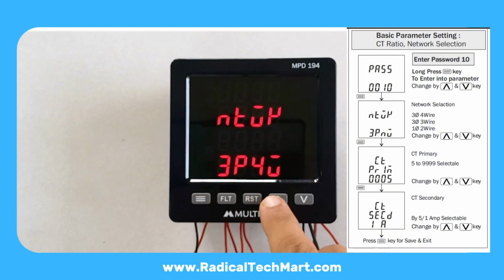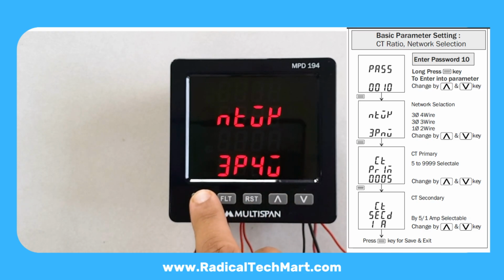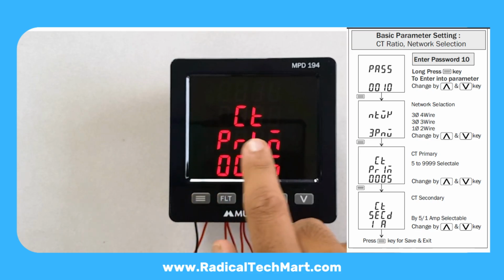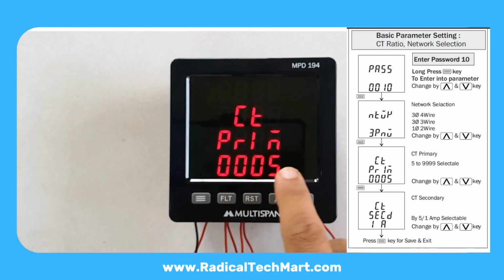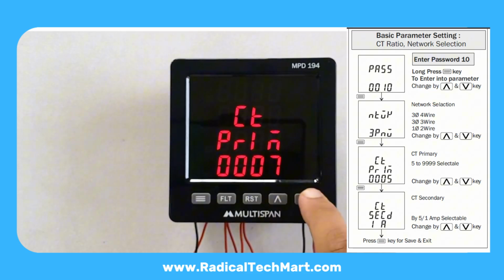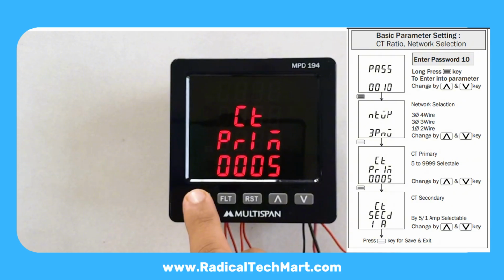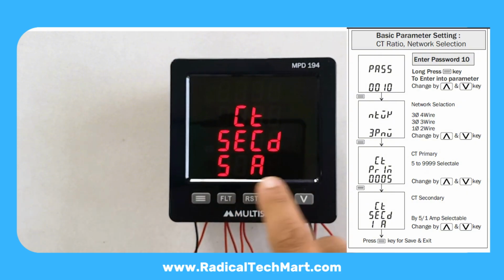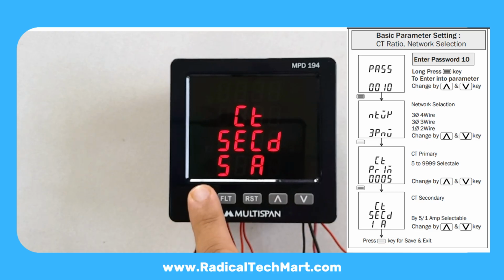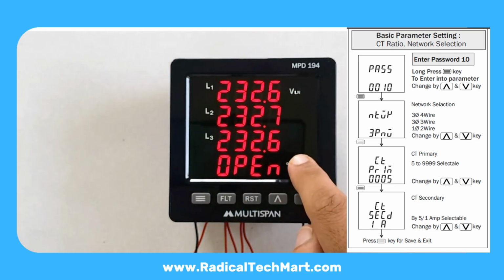Now you get the system type. Select from 3-phase 4-wire, 3-phase 3-wire, single phase. Select according to your system. Press set. Set the CT primary current using the up-down keys. Example, if your CT is 200 by 5 ampere, set the primary to 200 amperes. Press set. Select CT secondary, 5 ampere or 1 ampere. Press set to exit back to the main display.